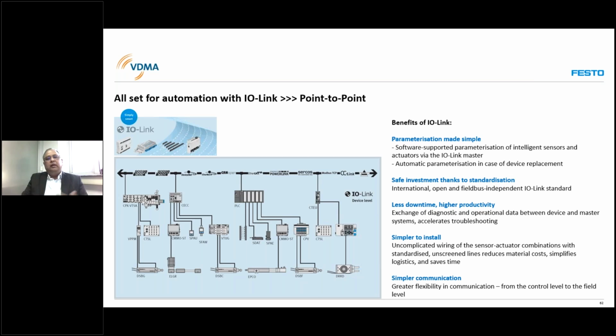Till now, let's say I give an example of a pressure sensor. A pressure sensor was being parameterized, taught values like threshold value, normally open, normally close, at what point it should switch off, and all these parameters were taught into the pressure sensor. Now when the signal was there, it was just communicating with the PLC, giving an output signal. PLC knows only that. When the PLC wants to communicate with the pressure sensor, that was not happening. When some data or parameters needed to be changed on the pressure sensor, physically the operator had to go to it, touch it, and change the values.